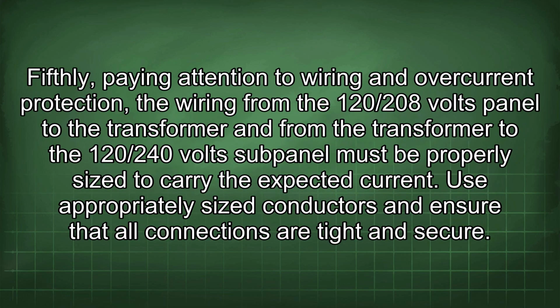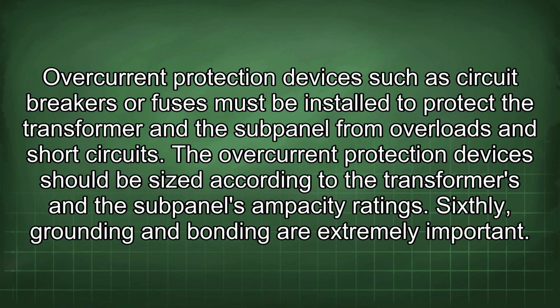Fifthly, paying attention to wiring and overcurrent protection. The wiring from the 120/208 volts panel to the transformer and from the transformer to the 120/240 volt subpanel must be properly sized to carry the expected current. Use appropriately sized conductors and ensure that all connections are tight and secure. Overcurrent protection devices such as circuit breakers or fuses must be installed to protect the transformer and the subpanel from overloads and short circuits. The overcurrent protection devices should be sized according to the transformer's and the subpanel's ampacity ratings.